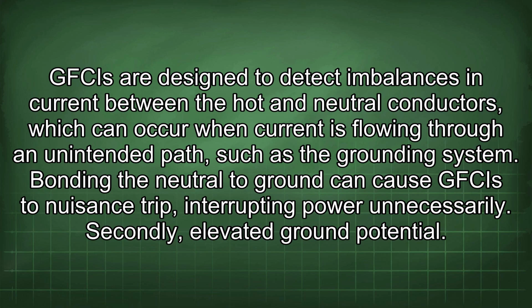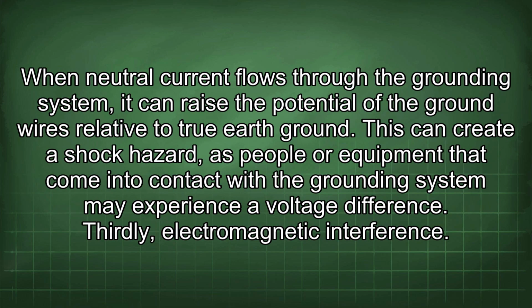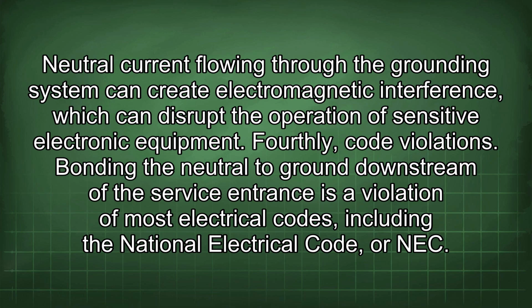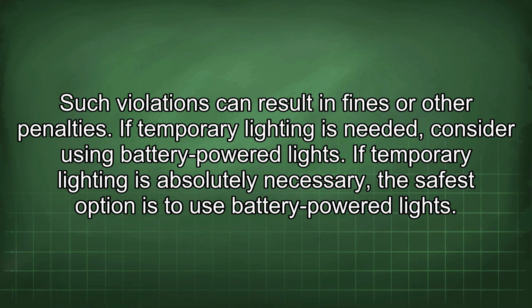Secondly, elevated ground potential. When neutral current flows through the grounding system, it can raise the potential of the ground wires relative to true earth ground. This can create a shock hazard, as people or equipment that come into contact with the grounding system may experience a voltage difference. Thirdly, electromagnetic interference. Neutral current flowing through the grounding system can create electromagnetic interference, which can disrupt the operation of sensitive electronic equipment. Fourthly, code violations. Bonding the neutral to ground downstream of the service entrance is a violation of most electrical codes, including the National Electrical Code, or NEC. Such violations can result in fines or other penalties.